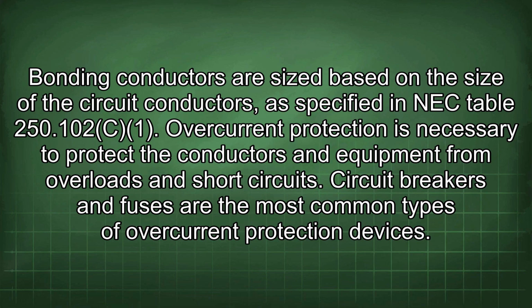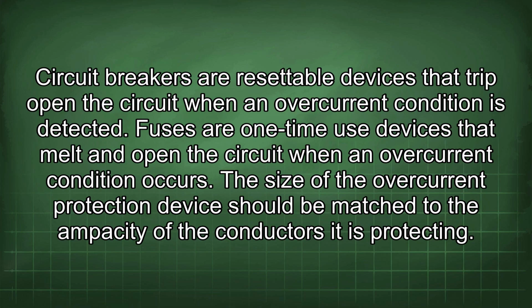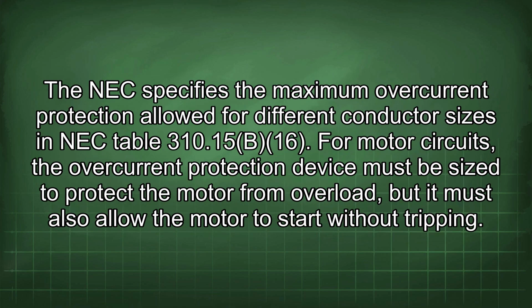Overcurrent protection is necessary to protect the conductors and equipment from overloads and short circuits. Circuit breakers and fuses are the most common types of overcurrent protection devices. Circuit breakers are resettable devices that trip open the circuit when an overcurrent condition is detected. Fuses are one-time use devices that melt and open the circuit when an overcurrent condition occurs. The size of the overcurrent protection device should be matched to the ampacity of the conductors it is protecting. The NEC specifies the maximum overcurrent protection allowed for different conductor sizes in NEC Table 310.15(B)(16).